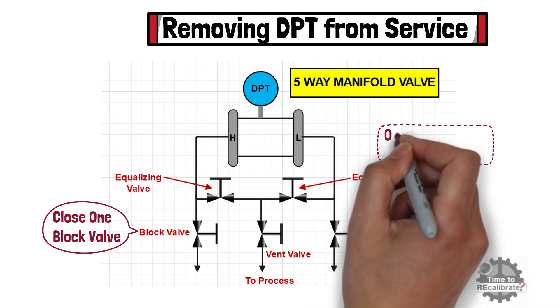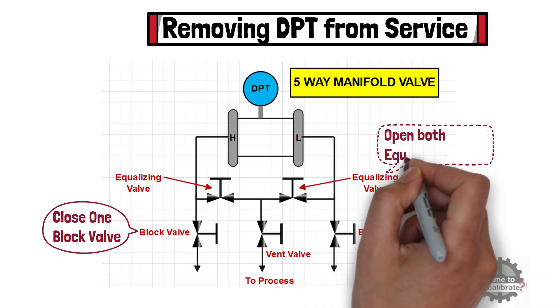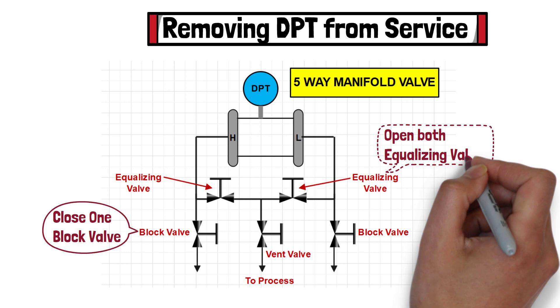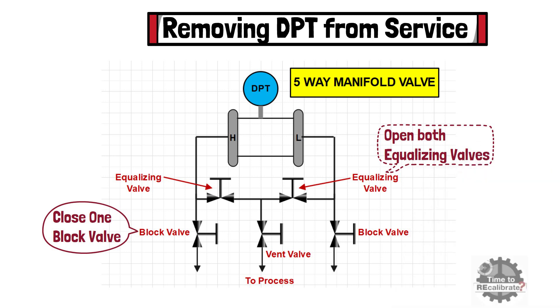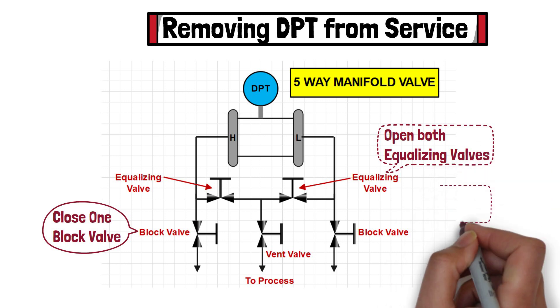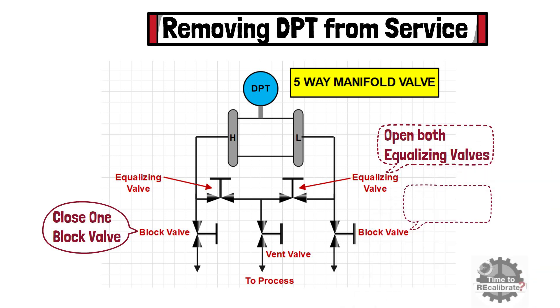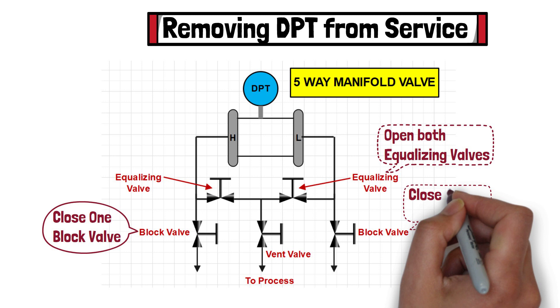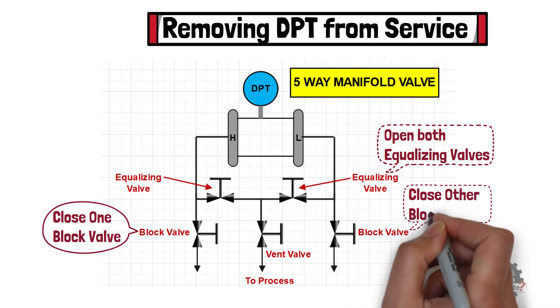Then open both equalizing valves — which one first does not matter. After this, close the other block valve.